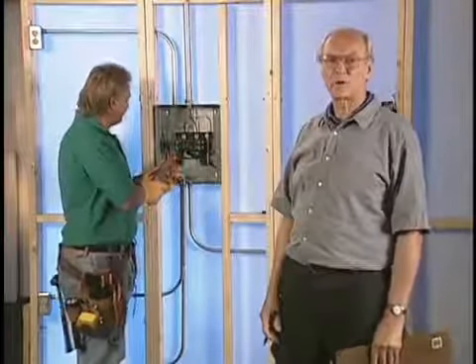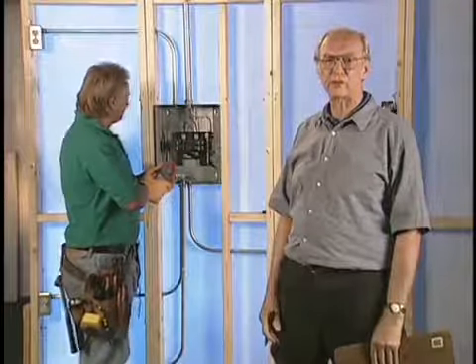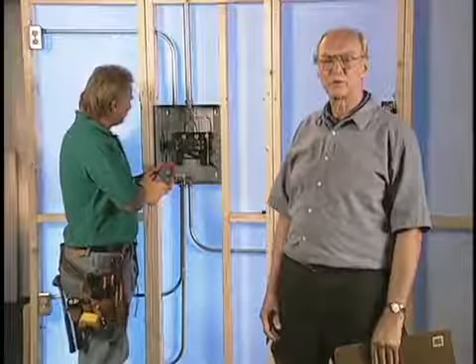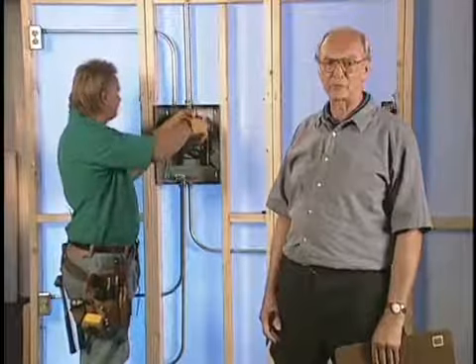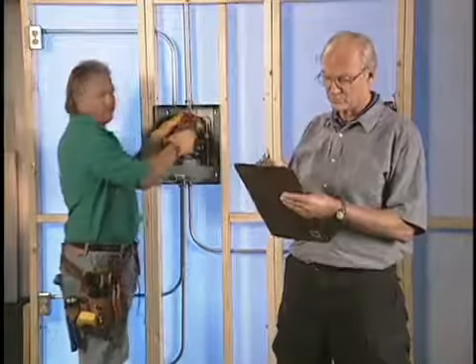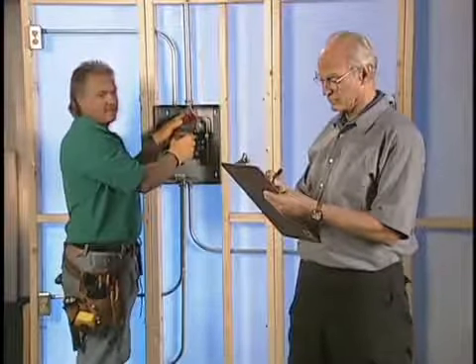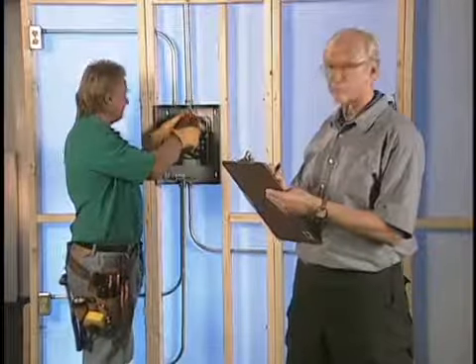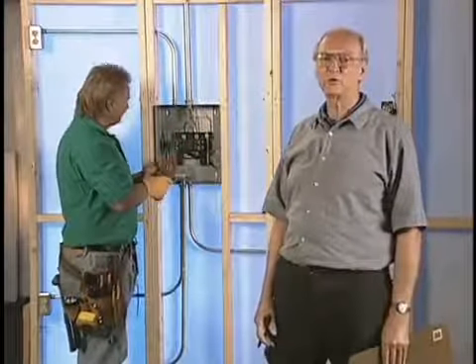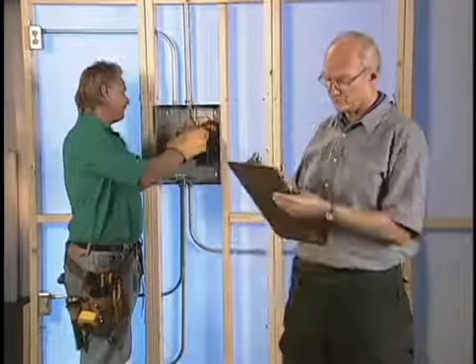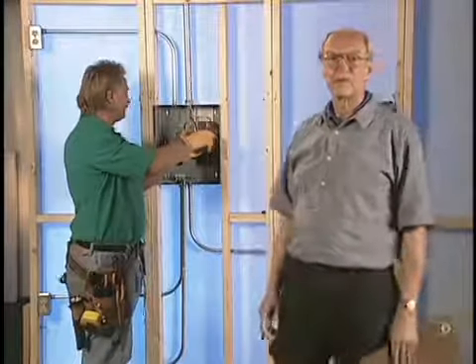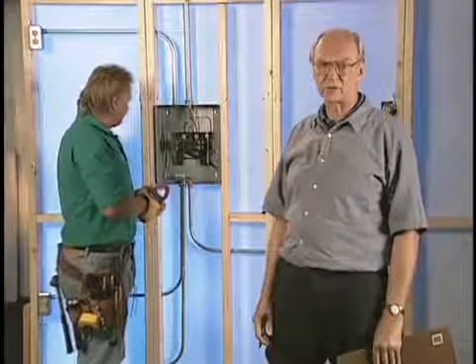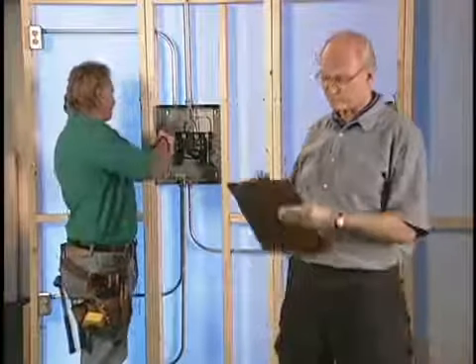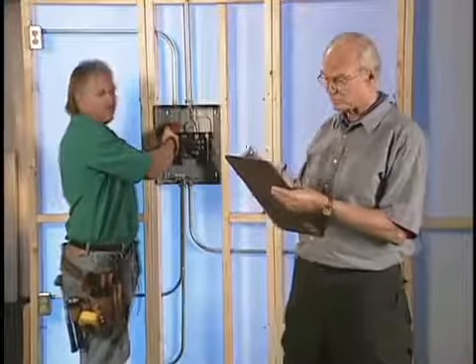Now we want to know, is this net current due to missing neutral current? First, clamp around the hots and record. 16 amps. Then clamp around the neutral and record. 8 amps. If there is an equipment grounding conductor, clamp around and record. 4 amps.